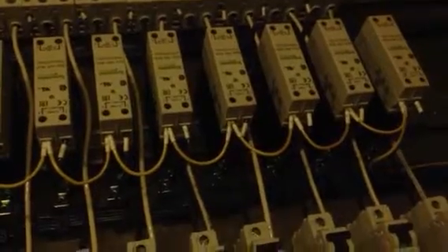Each circuit has a circuit breaker, which will be labeled and tagged. And it also has a solid-state relay. And even down below it has a GFI terminal block. I'm upside down here, so it may look a little odd, but anyway, thought this might help. All you really have to do is put your power in at the top. Down at the bottom, you hook up your heat trace directly to those GFI breakers. And then over here, you hook up your RTDs, labeled 1 to 12.